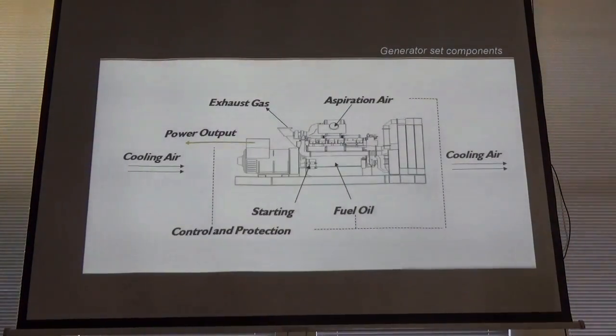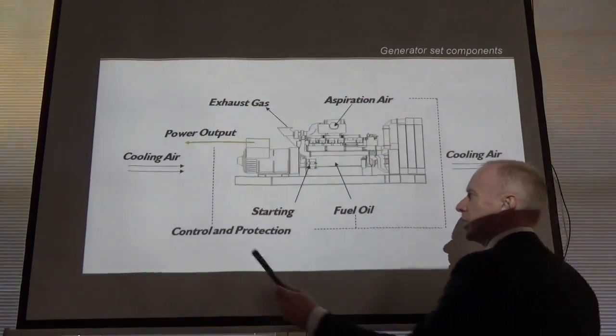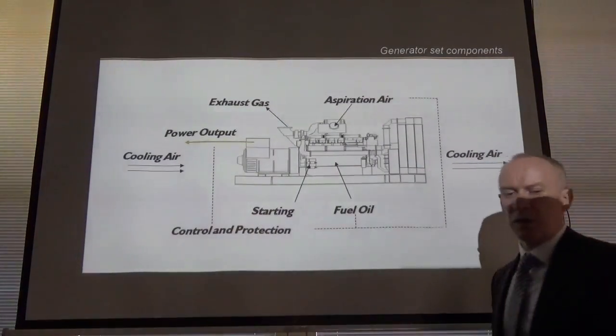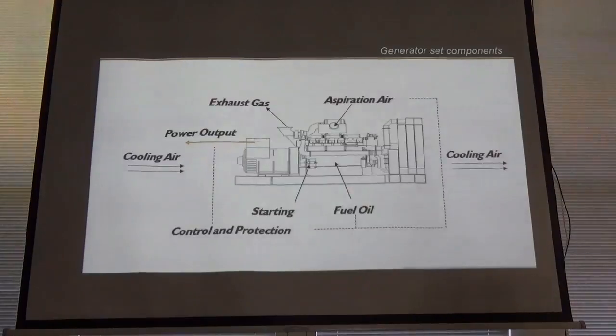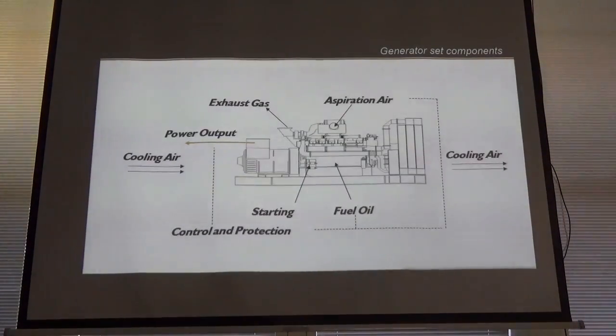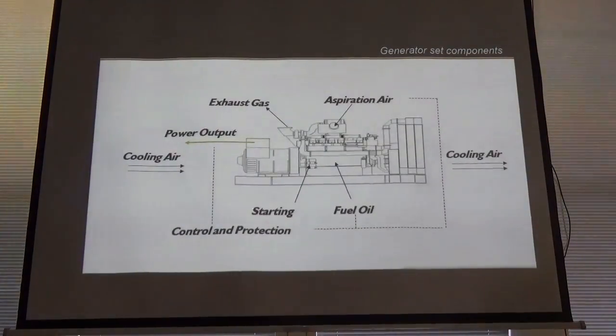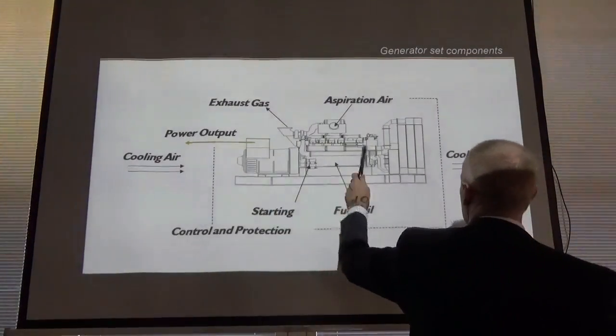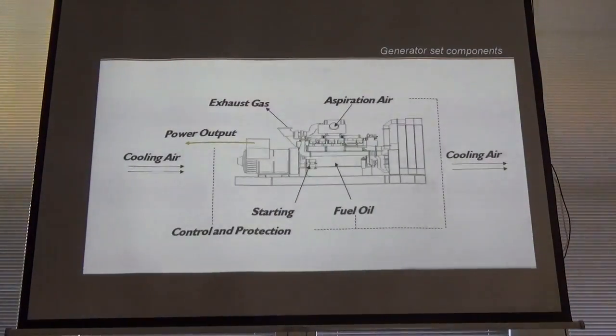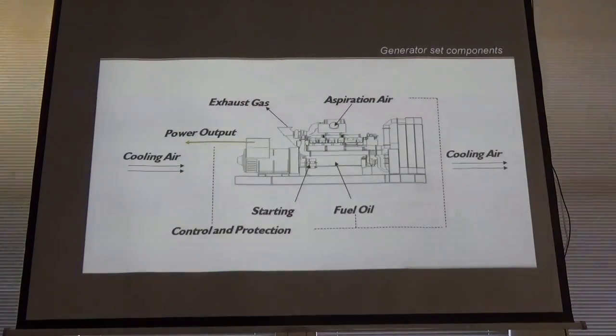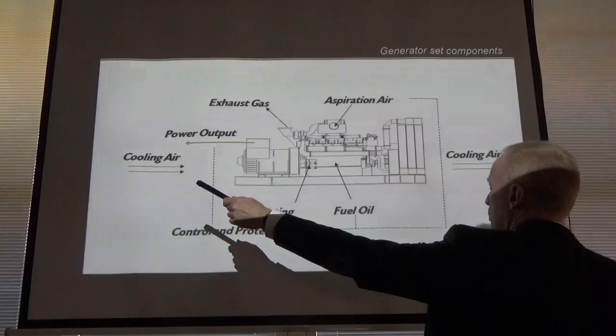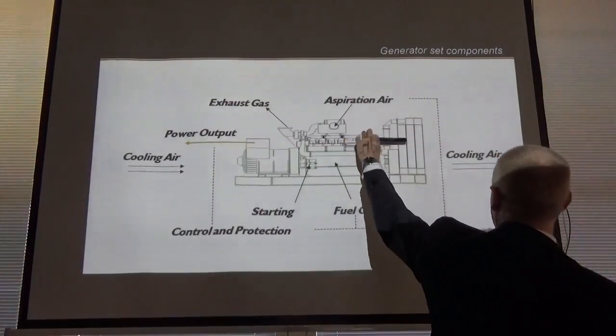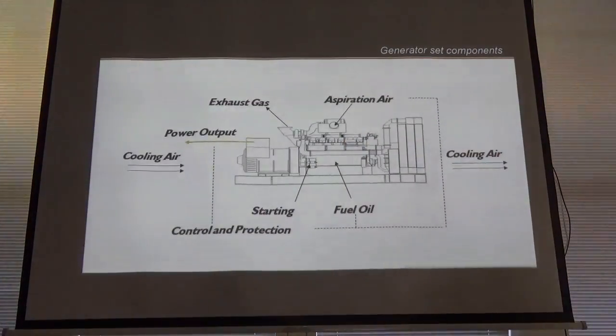You get an actual heat pickup. Say your outside ambient is 40 degrees centigrade. If that's 95-96% efficiency, given size and running at 100% of its rated load, you'll probably get a heat pickup of about 2 or 3 degrees C across that unit. Across the engine block itself, in turbos, you'll probably get a 5 to 6 degrees heat pickup. So essentially, if you're outside at 40, your air on temperature will probably be up to about 49 degrees centigrade.